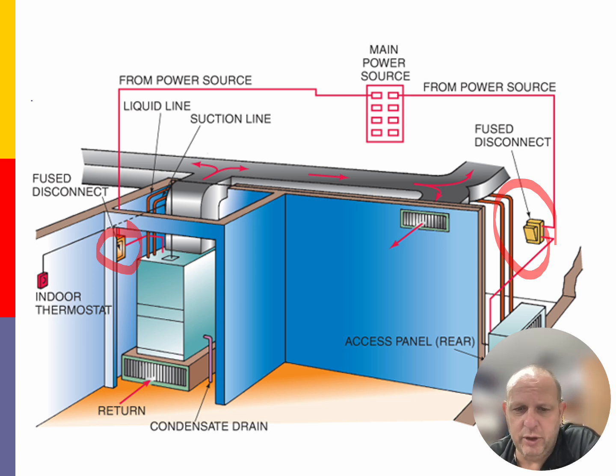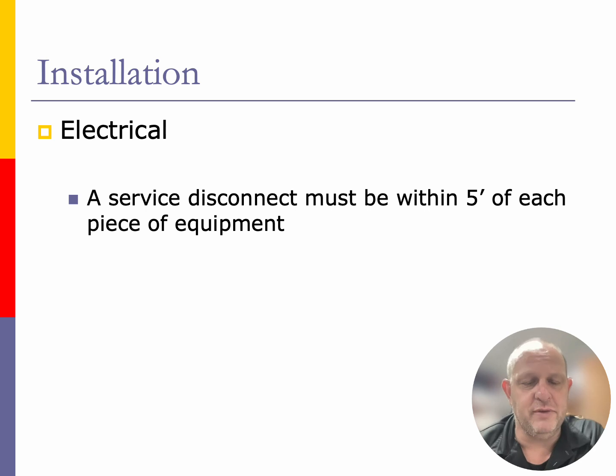This next picture that we're going to be showing you happens to be where we need to put the service disconnect for our particular units. The service disconnect is what we're going to be using to shut the power on and off to the outdoor unit. Now, this can be a straight switch, or it can be an actual breaker. We can have a breaker, we can have fuses, we can have just a normal square D switch, but it has to be within reach of the outdoor unit, or within 5 feet of the outdoor unit, so we can quickly shut off the unit for servicing.